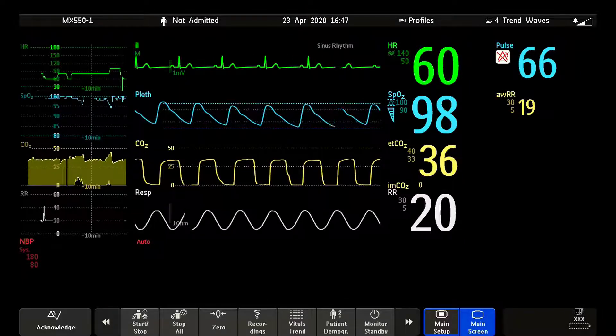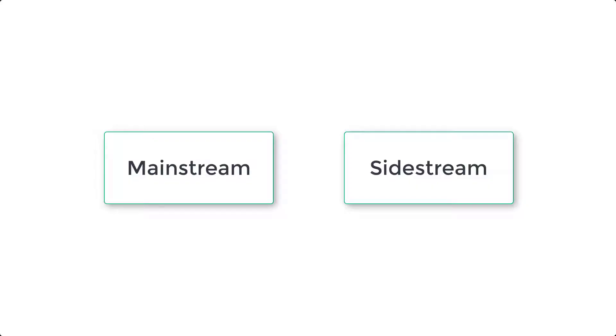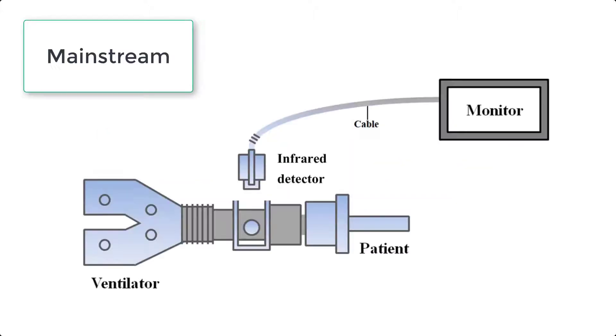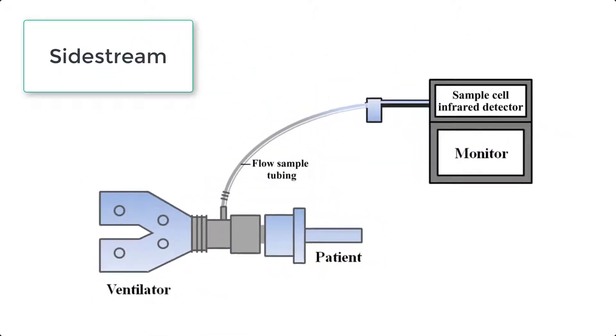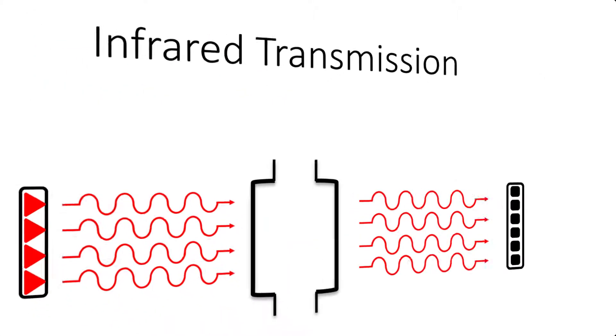In the IntelliVue patient monitor family, there are two methods for measuring CO2 in the patient's airway: mainstream and sidestream. The mainstream measurement uses a CO2 sensor attached to an airway adapter directly inserted into the patient's breathing system. The sidestream measurement takes a sample of respiratory gas with a constant sample flow from the patient's airway and analyzes it with a remote CO2 sensor built into the measurement system.